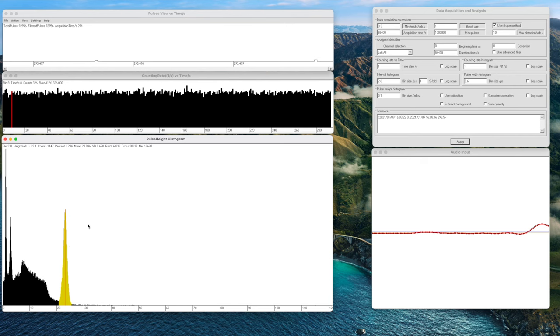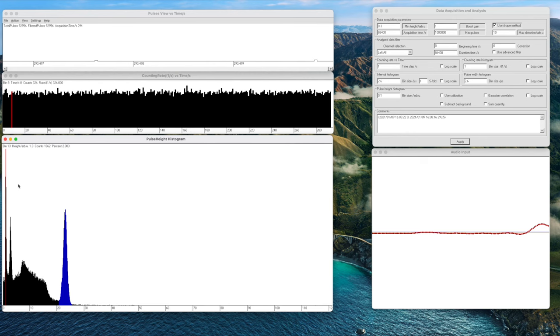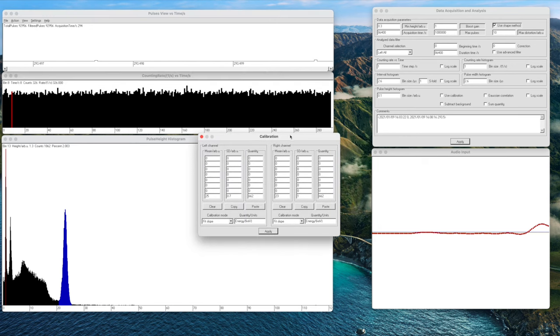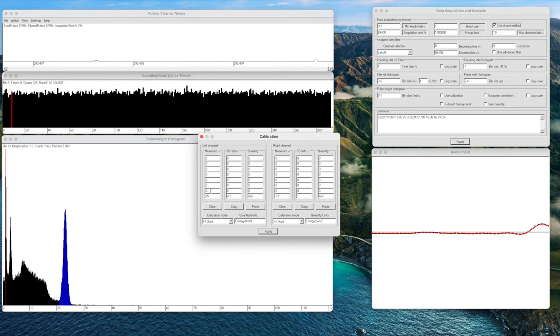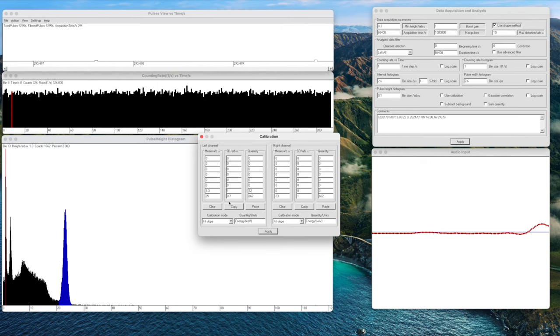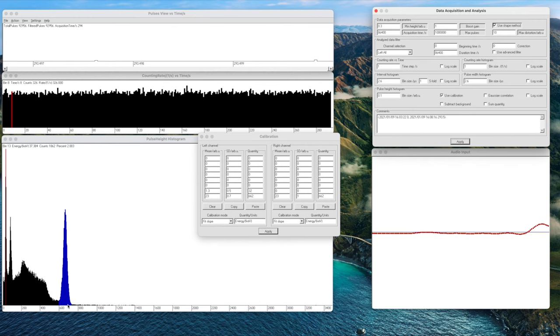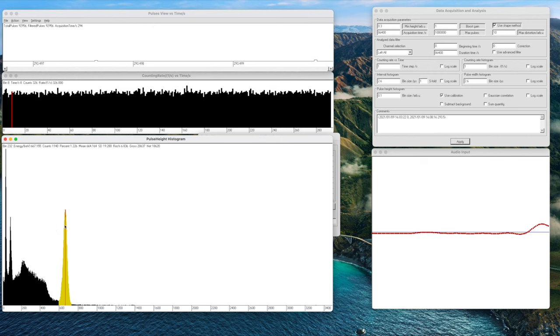If we look at the x-ray peak we can see that that is at arbitrary units 1.3. So let's go to calibration and we simply enter these figures here. We have 1.3 and I'm just going to put a 1 in there for the minute. That is our 32 kiloelectronvolt x-ray. Then we had at 23 arbitrary units we had our 662 cesium-137. We'll click apply and then when we switch on energy calibration on the data acquisition and analysis panel and apply, we can see that the x-axis has changed itself now to energy and we should have 662 right on there. So it's as simple as that.